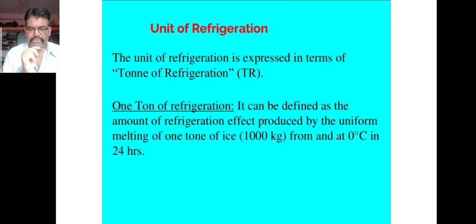So the calculation: 1 ton of refrigeration, that is TR, is equal to 335 multiplied by 1000, where 335 kilojoules per kg is the latent heat of ice, divided by 24. It means 13958.33 kilojoules per hour. If it is converted into minutes, then it is 232.6 kilojoules per minute, or approximately 3.88 kilowatt in the SI unit.